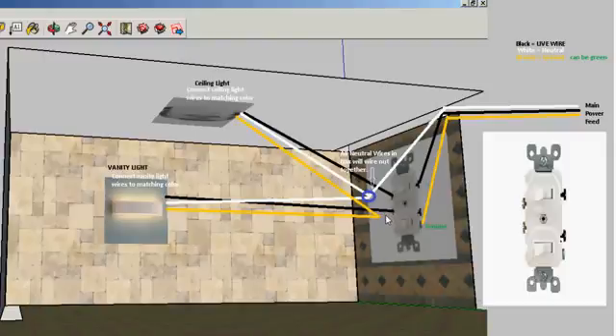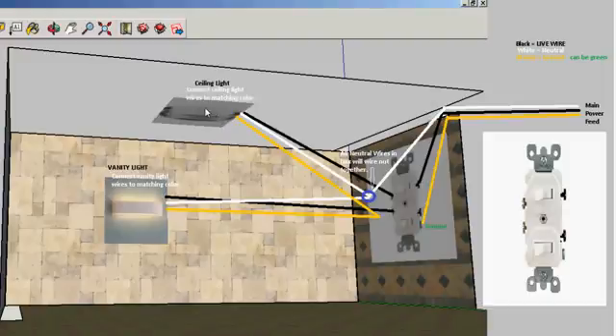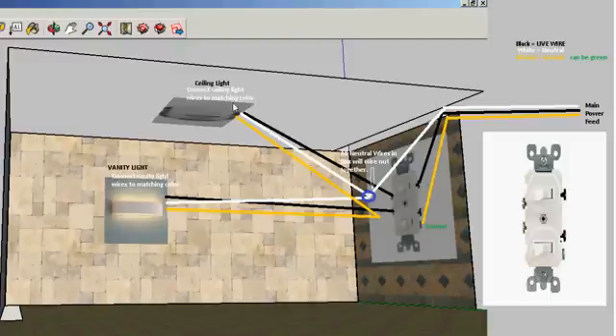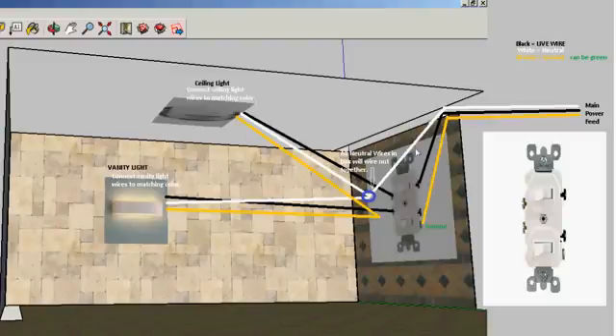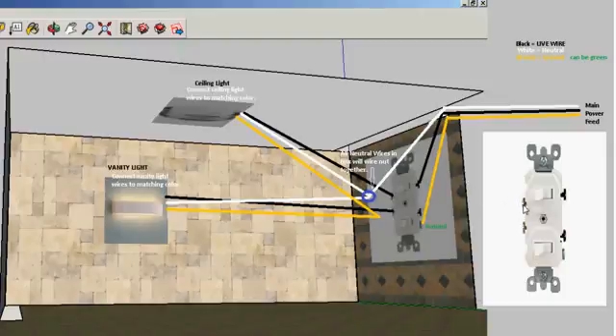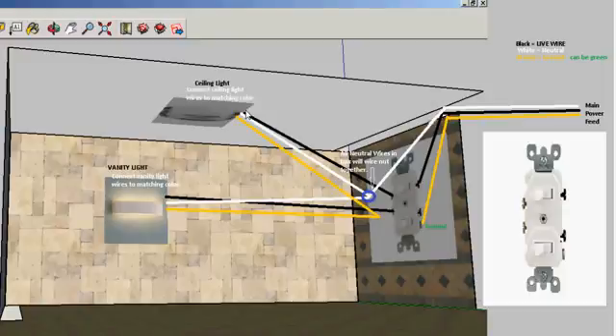In this case, this one actually did have a grounding wire built in with the ceiling fan. So this grounding wire is grounded with that, and then this is grounded to metal. Like I said, all three neutrals - neutral from the ceiling light, neutral from the vanity light, neutral from the main feed - are connected together. They will not be put on the light switch at all. And then last but not least, you have the black feed, the hotline coming from the bronze on the double switch going to the black wire on the ceiling light. Wire nut that, tape that, and you should be good.